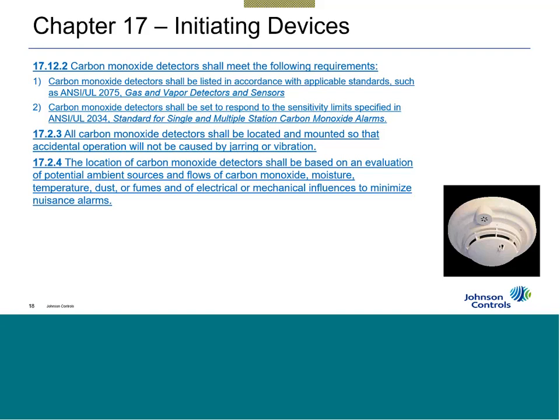I can't tell you how many times I've gone to installations or talked with people, and I said, why do you still have the orange covers on the carbon monoxide device? Well, the building's not being taken over for a few more months, and we want to make sure that the timer doesn't start, and we don't want to expose the device to the atmosphere and change that time. We want to get the full 10 years out of it. Sorry, as soon as I manufactured it and it left the line, the clock started ticking. So you need to look on the back.